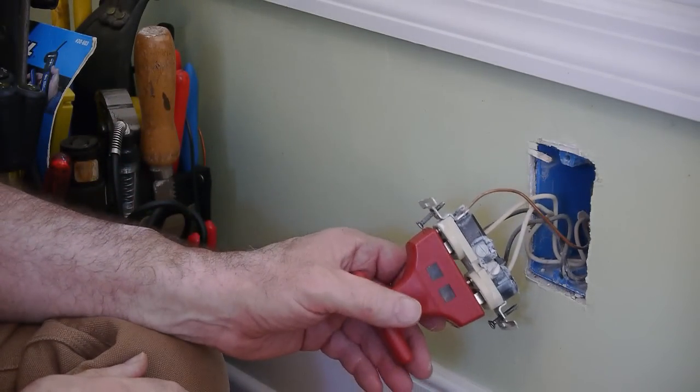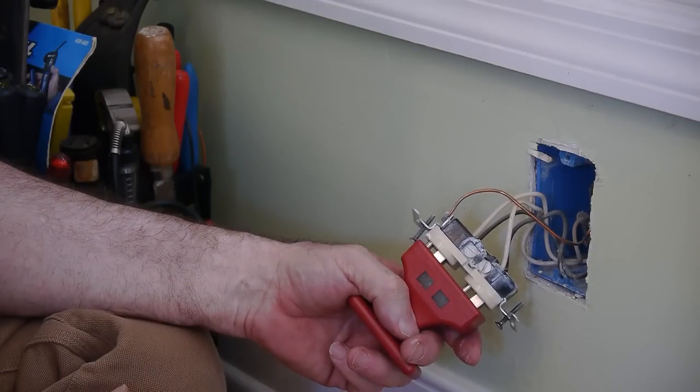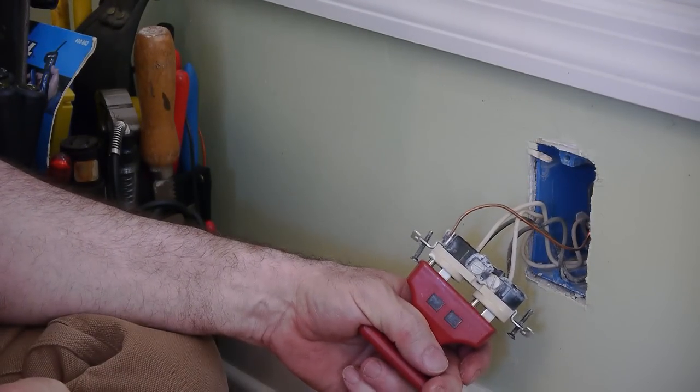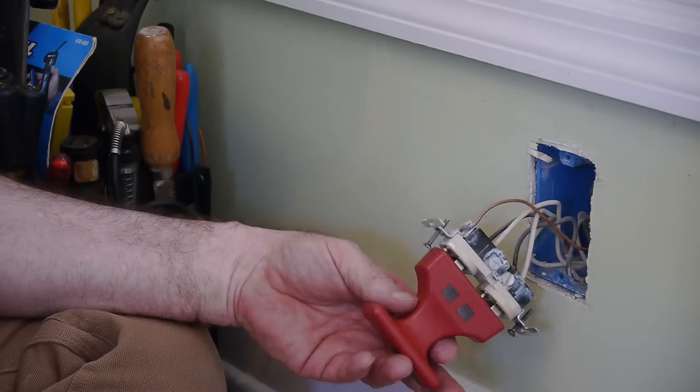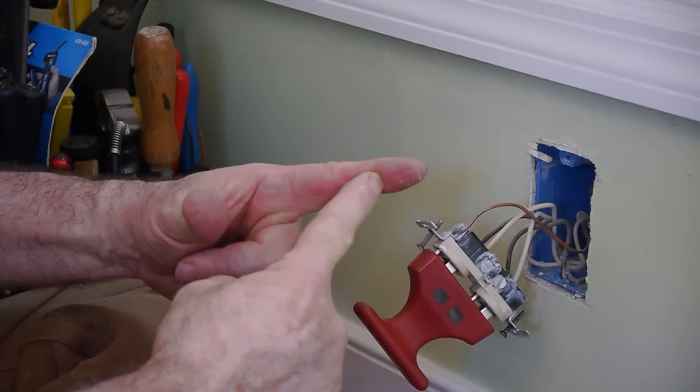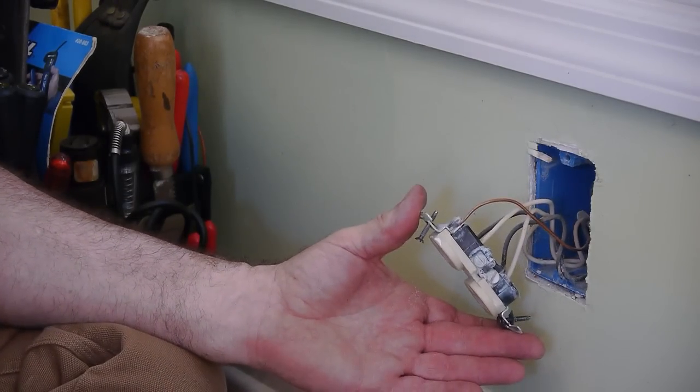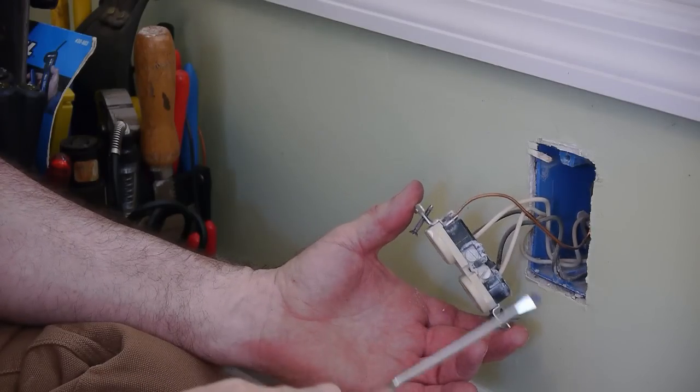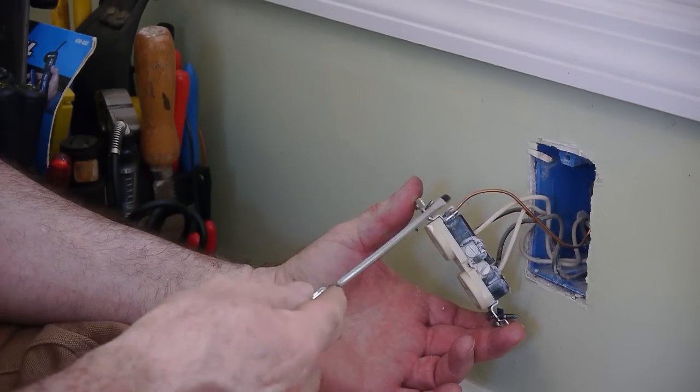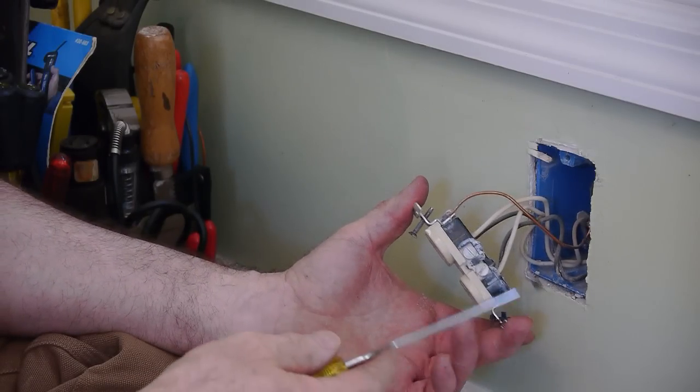This is another one of my pet peeves. I was sure this was going to happen because I've changed other outlets in this house. You see the wires are just stuck into the back, which is an acceptable practice I guess sometimes. Now this plug they seem to be pretty secure. So it probably has some clamping. It probably clamps down. But I've seen them before where they stick in the back and there's nothing but a little one little tab of metal holding the wire. It just contacts in one place. I'm going to go ahead and take this out the rest of the way and see what's going on in there. But it is good. We've got the ground is connected to the ground. You know it's got a plastic box. So if you have a metal box a lot of times people will not ground it because it's grounded to the box. But a lot of times the box isn't grounded. So I always ground them.